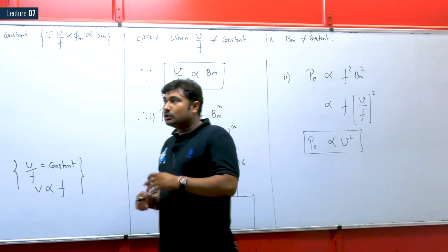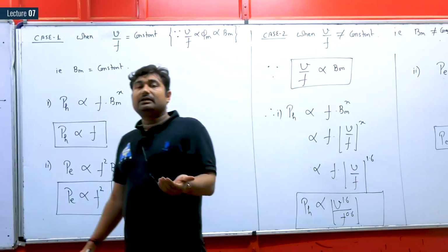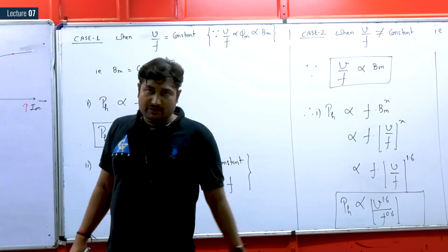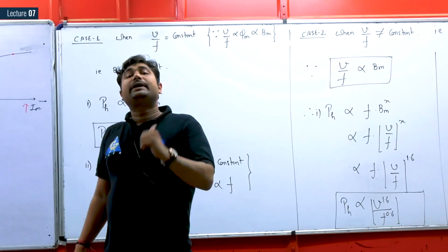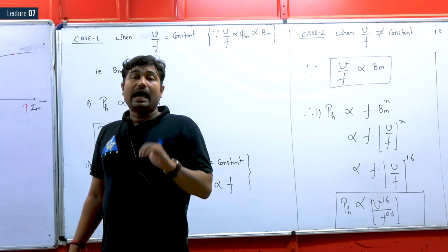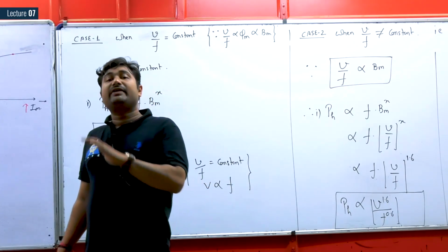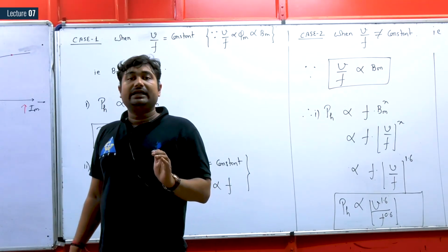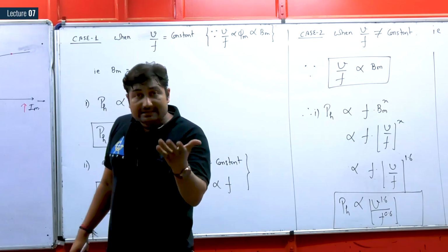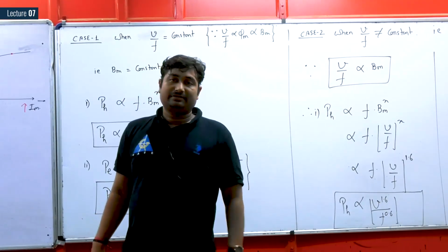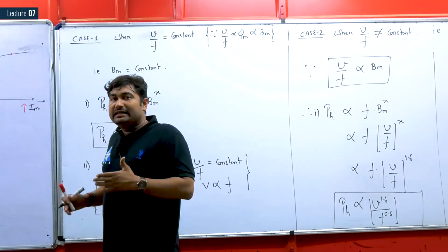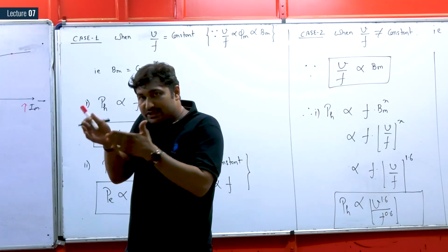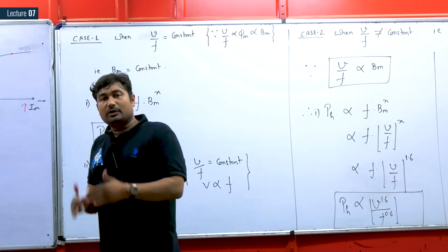So it means, though I have mentioned the total efficiency of the transformer on the nameplate of the transformer, if you are not operating the transformer at a specified voltage and specified frequency, then definitely the core loss, which you treat as a constant loss, is going to change. So if you change the operating condition defined by the designer, definitely you will not achieve the efficiency defined by the designer. The losses are going to be affected.